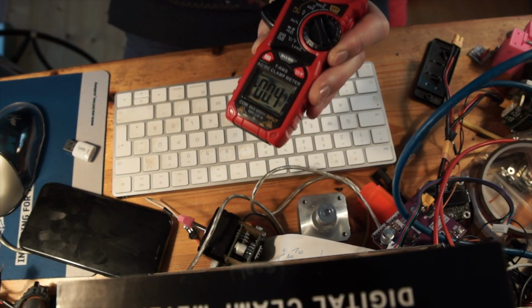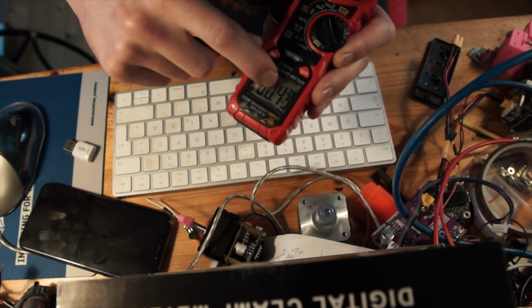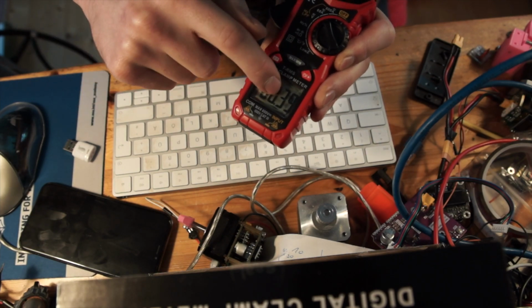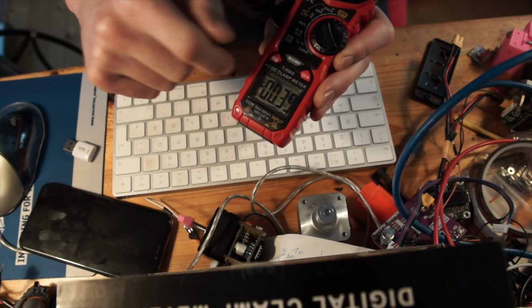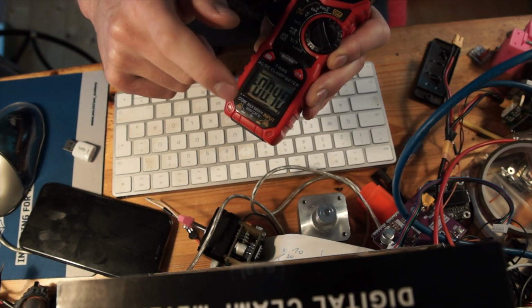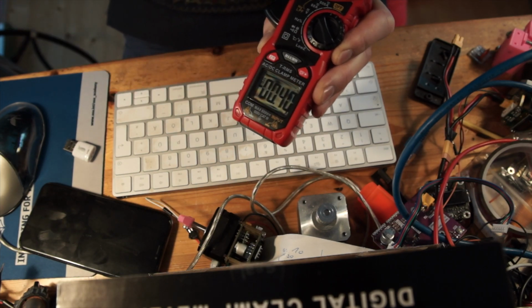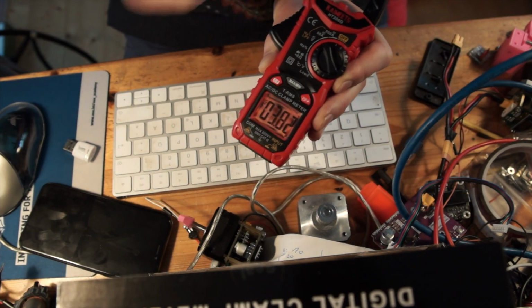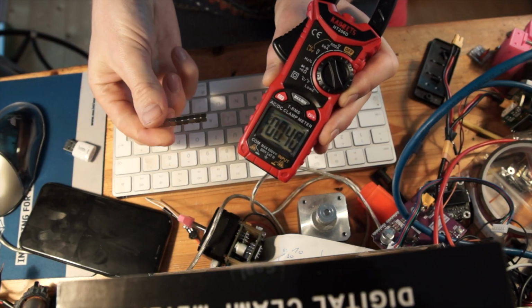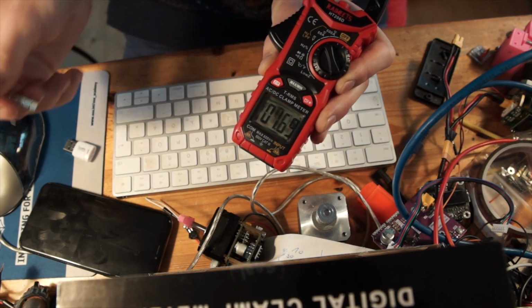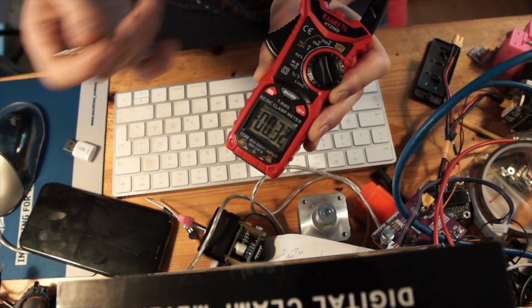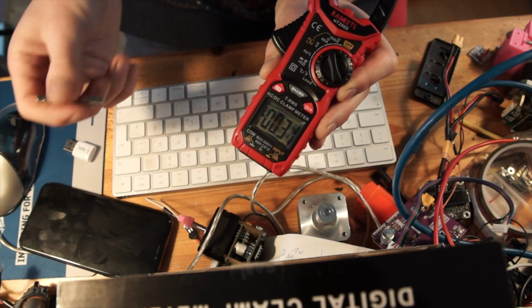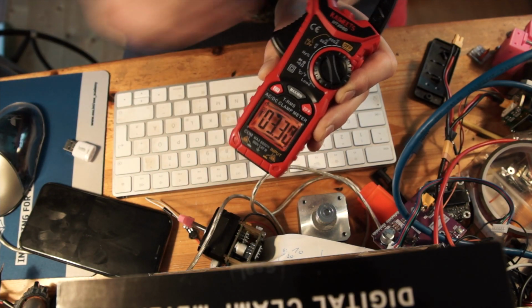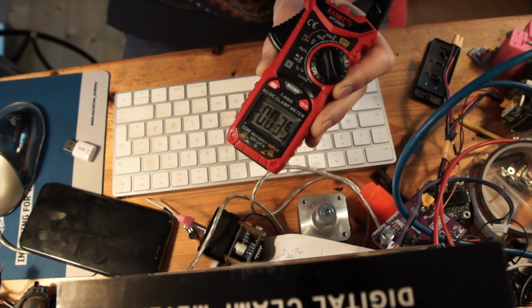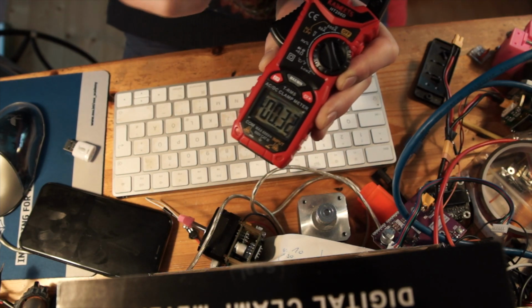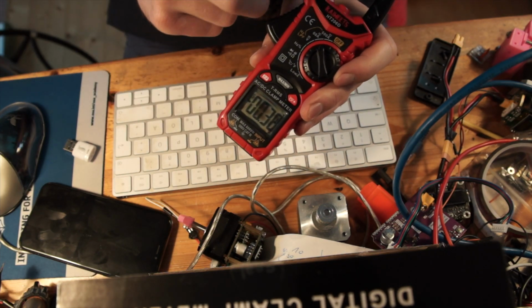Yeah, the problem is that I have a tiny offset on the DC measurement, and this is maybe due to magnetization of the clamp head or maybe due to some missing calibration. They work by measuring with a Hall effect sensor the magnetic field strength in the clamp. So having a magnet or magnetic metal stuff nearby definitely affects the readings. So keep these away while measuring and also keep them away while storing them because you can magnetize the clamp.